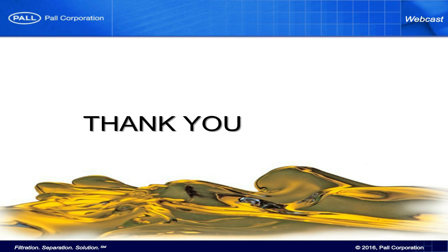James asks, what happens if you don't have dry air available to use in a purifier? That's a very good question. What happens to air coming into a mass transfer purifier? It comes into an area of vacuum, so typically the air will expand as it comes into the chamber. Depending on the level of vacuum, for example, the air will expand 5-fold, and as it does that, its relative humidity drops by the same percentage. And that is the key.